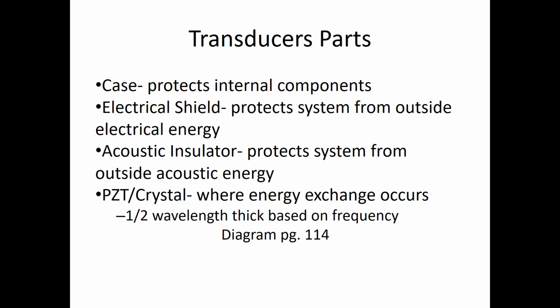And then we have the actual PZT or the crystal. This is where the energy exchange occurs. Lead zirconate titanate, that's the PZT. So electrical impulse goes into this, piezoelectric effect happens. The electrical impulse kind of shakes those crystals up and they emit acoustic energy. That acoustic energy goes into the body, reflected back at a specific amplitude, and then that's turned back into an electrical impulse. And then we look at it and see, hey, is it bright or is it not bright?